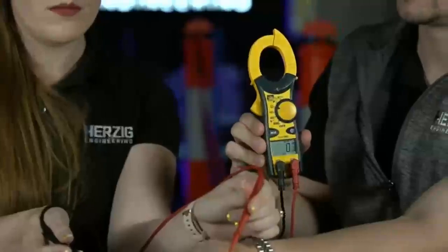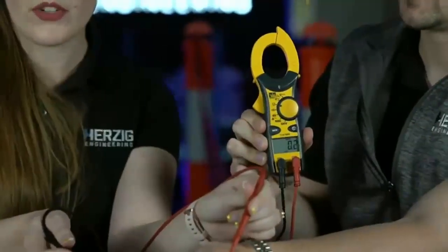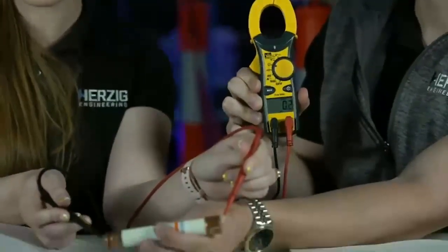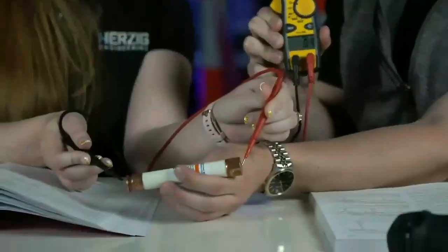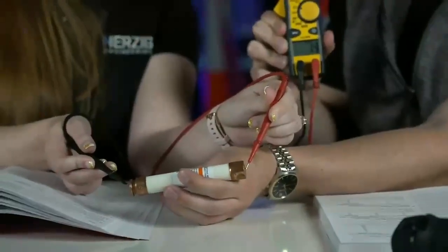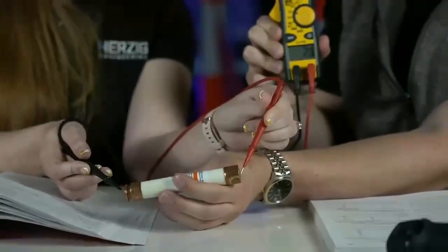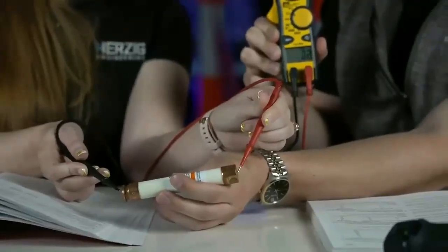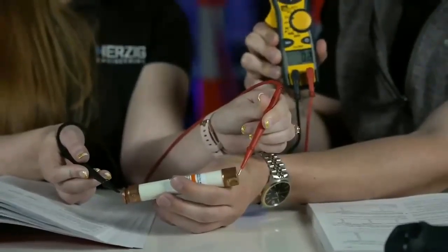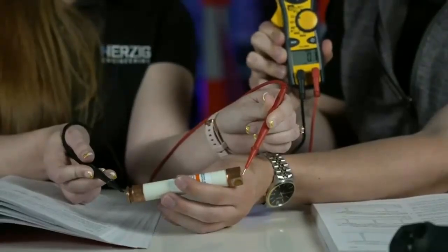So it's real simple. You literally just check to make sure that there's not excessive resistance. And ideally, what you want to look for is between 0 and 5 ohms. And if I stop moving, it'll not have resistance. Sorry. But closer to 0, the better. And we're at 0.1. You can see that this is a good fuse right here.